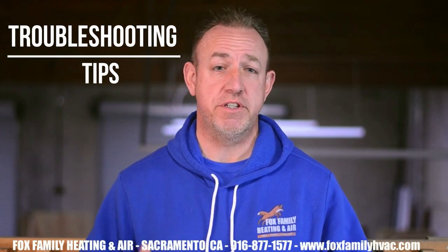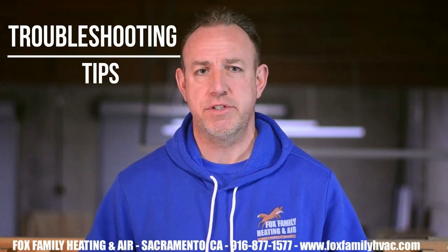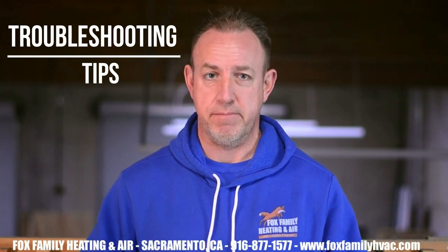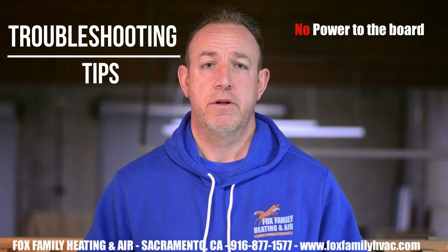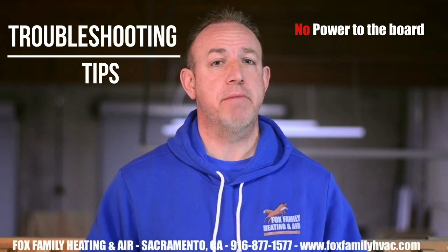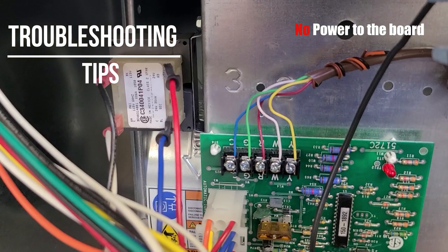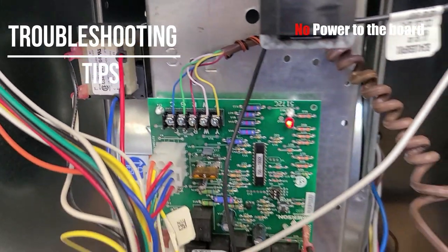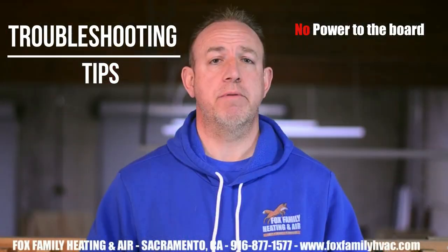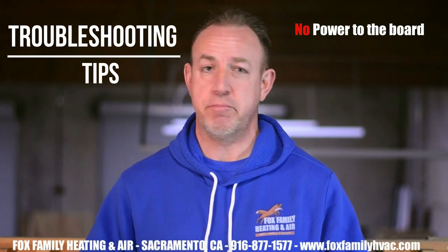Here are some things that can happen when the furnace isn't starting up correctly. These troubleshooting tips are not all inclusive and are not to be taken as scripture — these are general problems only. No power to the board: if the unit is plugged in correctly and the breaker at the main panel is in the on position, there should be power to the furnace control board. There's also a transformer that can go bad between the outlet and the control board, and they can and do fail regularly. The board with proper power can then send the high and low voltage signals it needs to run the relays.